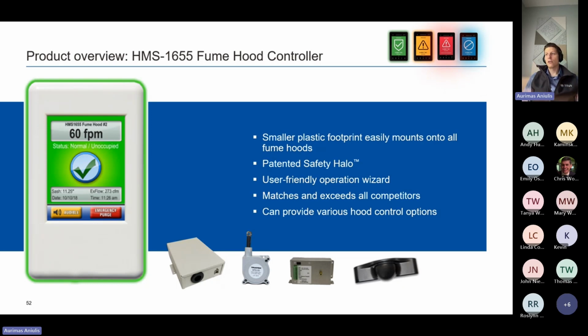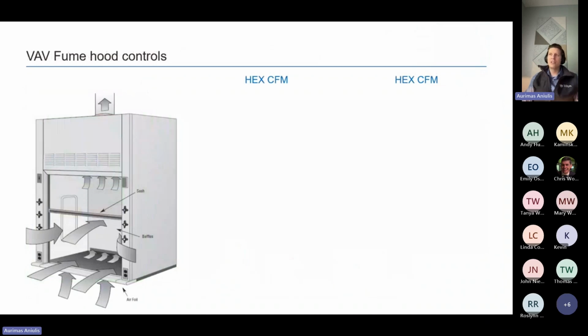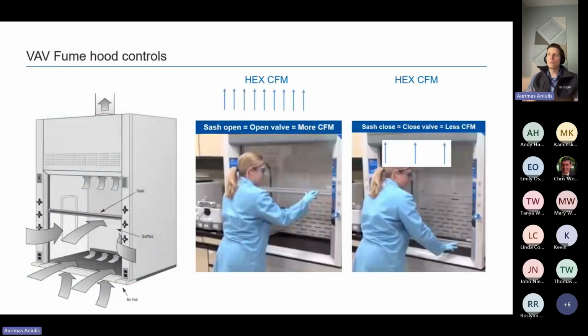Our fume hood controller, again, we're working to upgrade this to our 2000 display, but it comes with the fume hood controller, same hardware as the room level, different software. It comes with our sash position sensor, a sidewall differential pressure sensor, and an optional occupancy sensor. And fume hoods are, to me, the center point of critical environments. They are the most critical piece of HVAC equipment in a lab.